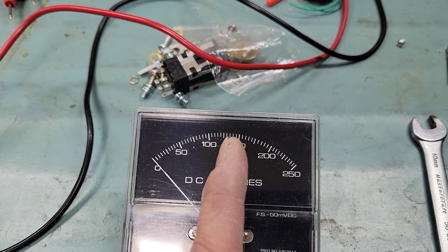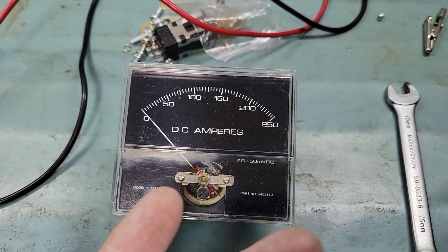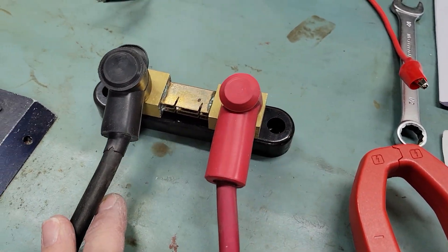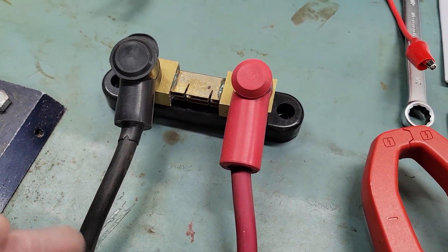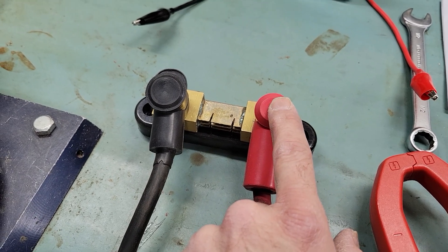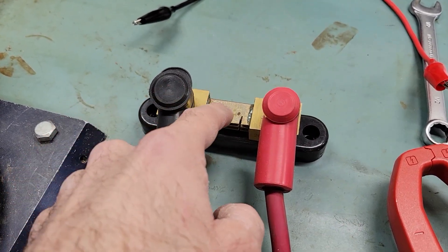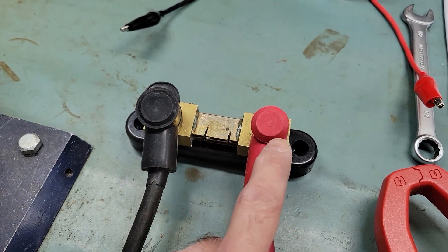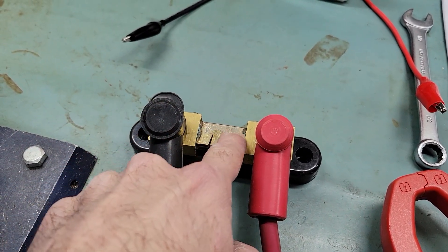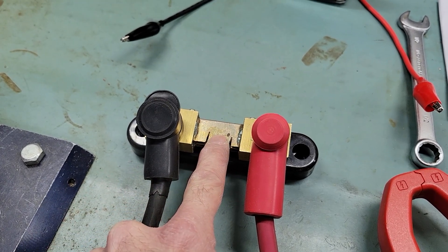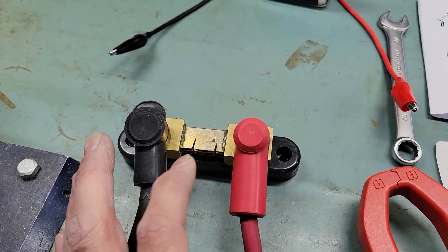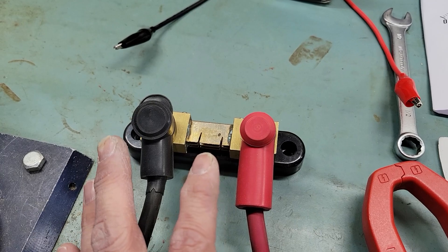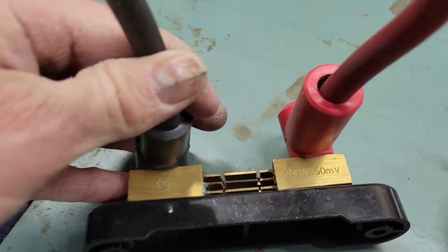Those millivolts come from what is called a shunt. A shunt is in fact a kind of resistor, a calibrated precision resistor normally that you will connect in series with your circuit and it will create a voltage drop. When there's a given current, this kind of resistance here will have a voltage drop because it's not a perfect conductor.